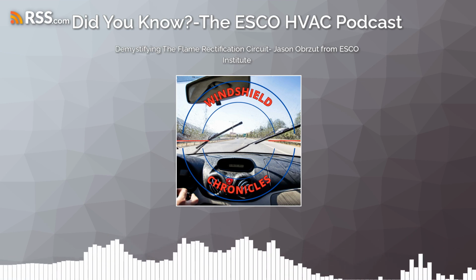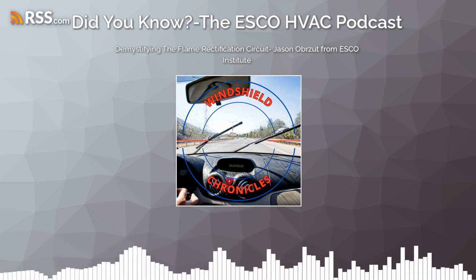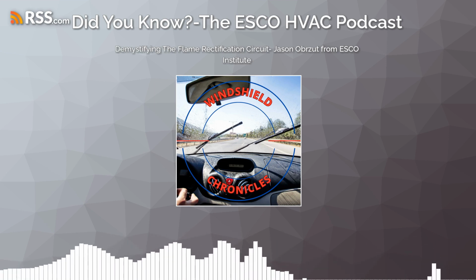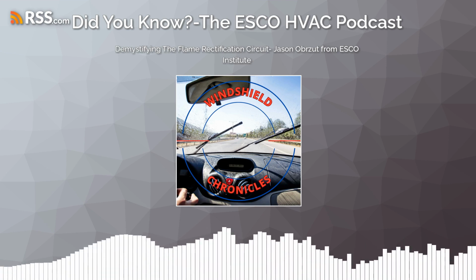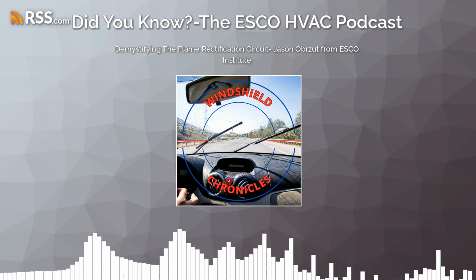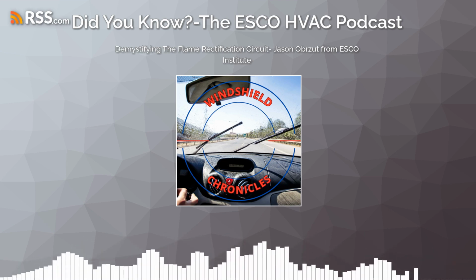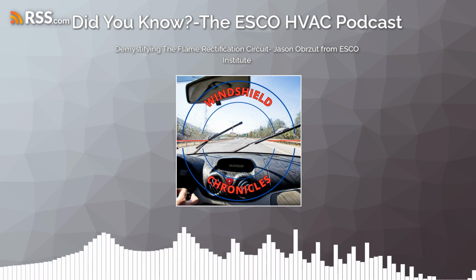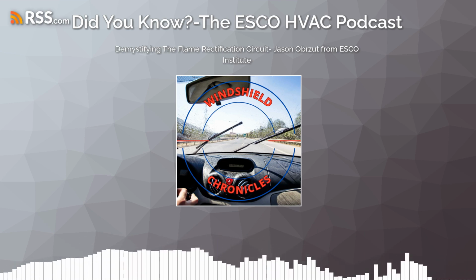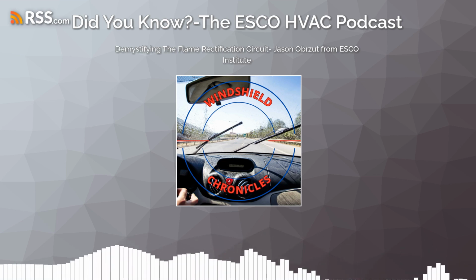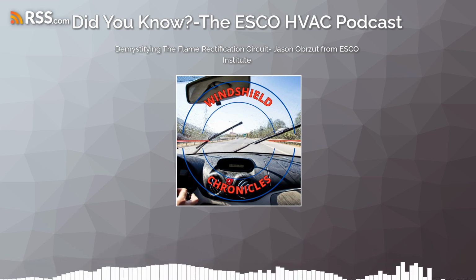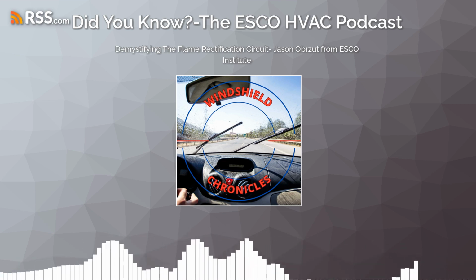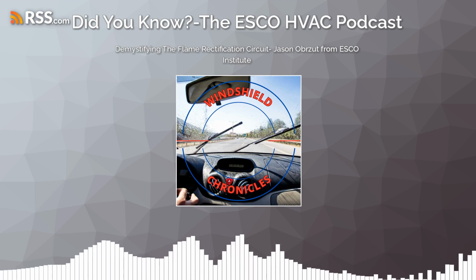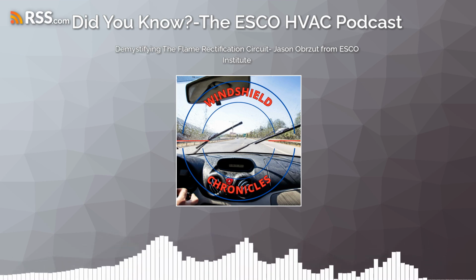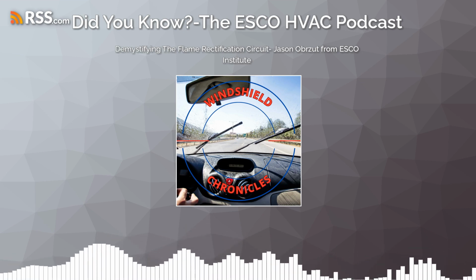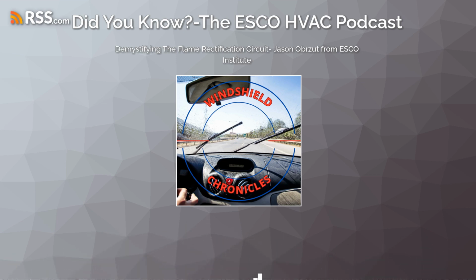It all goes way back into the early 1800s when Thomas Johann Seebeck found this really interesting effect. When he applied heat to dissimilar metals, it created a magnetic field. Electrically, a magnetic field can turn into current when we utilize it properly. So we started experimenting with thermoelectric current as early as 1821. What does that mean to us? That's the technology we put into play in thermocouples, and there are still thermocouple driven devices out there. But the difference between thermocouple and flame rectification is very different. So if you learn from someone who understands thermocouples and you move to flame rectification, you may not have gotten the full clarification.